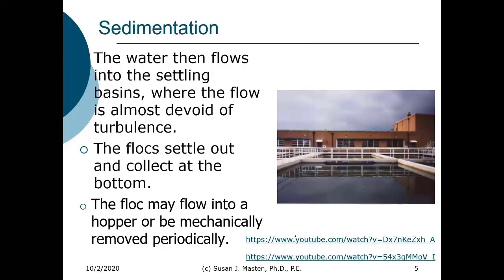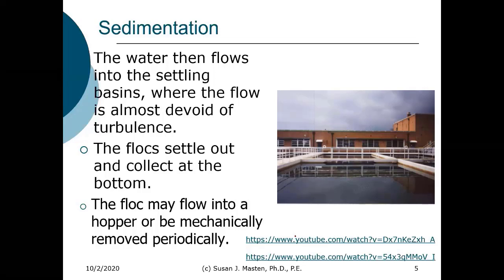When we're talking about sedimentation, the water is flowing into these typically larger basins, often operated as a plug flow or nearly plug flow system. The goal is that the water is almost devoid of turbulence. We want to allow the flocs, or the precipitated calcium carbonate or magnesium hydroxide, to collect and settle at the bottom. The floc may then flow into a hopper and be mechanically or pumped physically removed from the system.